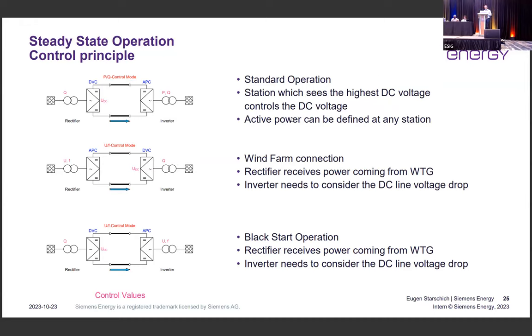Very important to mention is that we have different control principles. In all the systems in operation so far, we usually have the so-called PQ operation mode, where the active and reactive power are defined by the operator, or we have the UF control mode, where the voltage and frequency are defined by the operator, and the power flow is defined by the network operation. For example, the most common case is the wind farm connection.